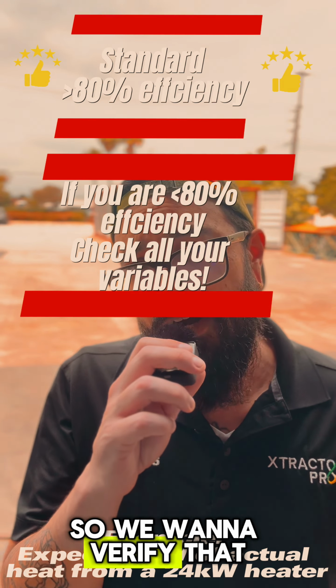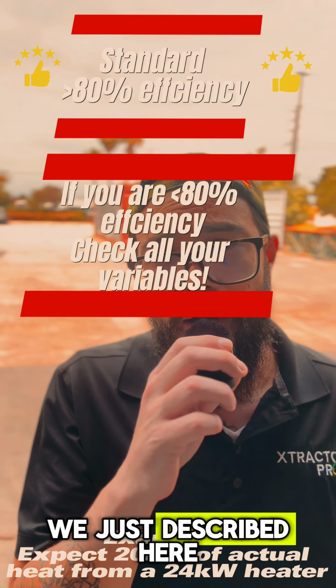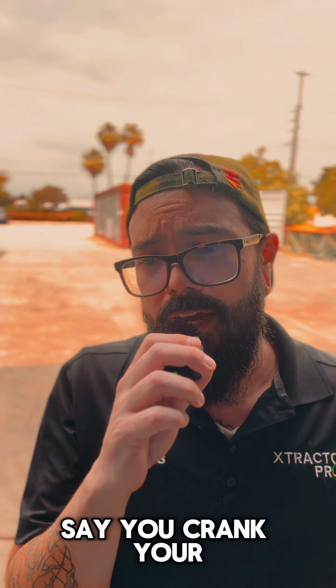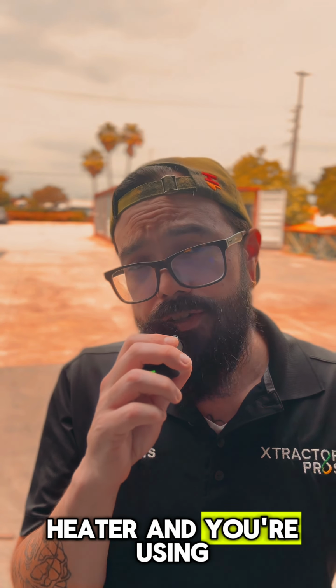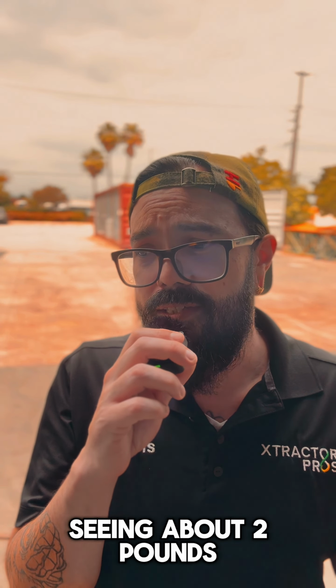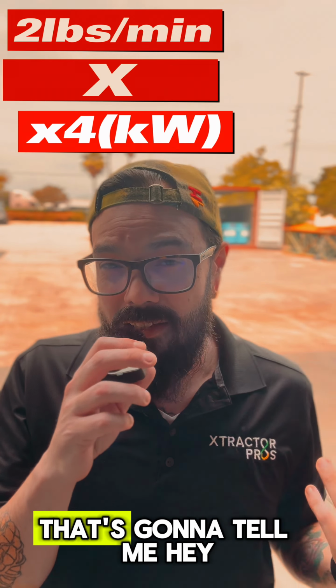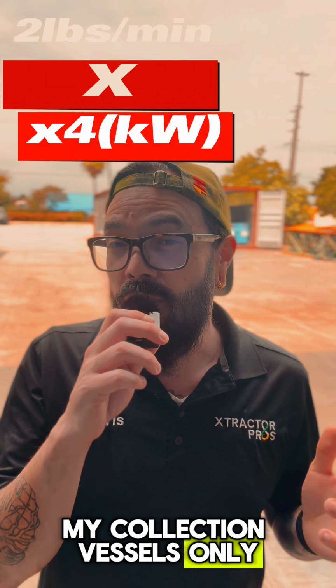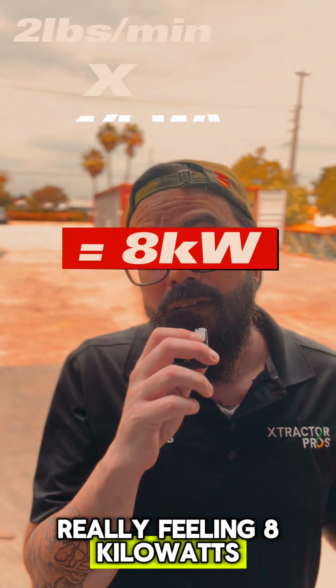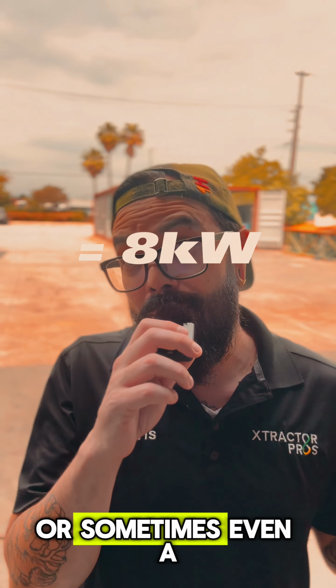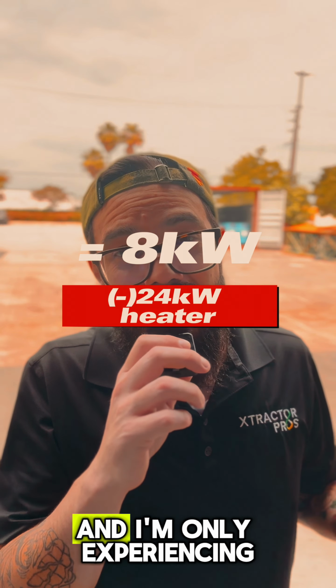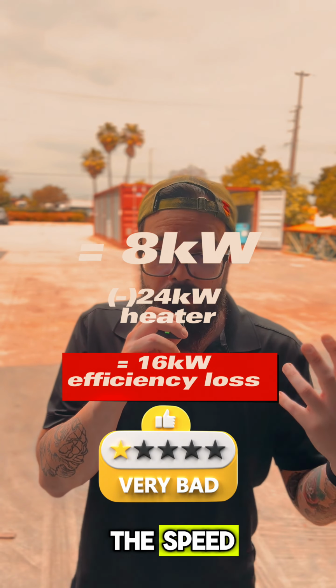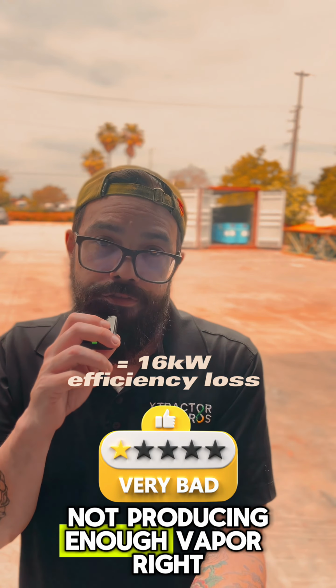So we want to verify that, and the test we just described will help you verify. Say you crank your heater and you're using dry ice, and we're only seeing about 2 pounds per minute. That tells me my collection vessel is only really feeling 8 kilowatts. So if I have a 24 or sometimes even a 48 kilowatt heater and I'm only experiencing this speed, it's because we're not producing enough vapor, right?